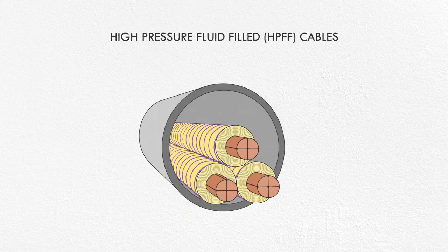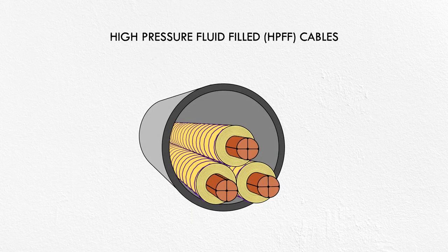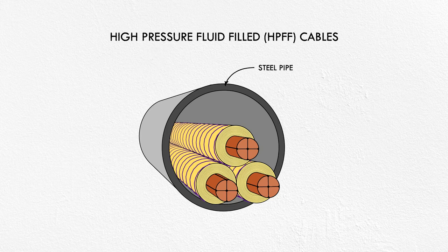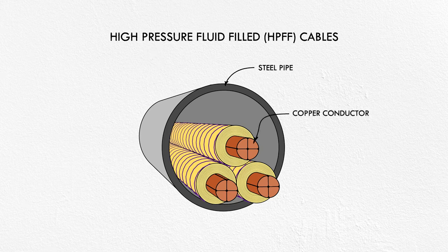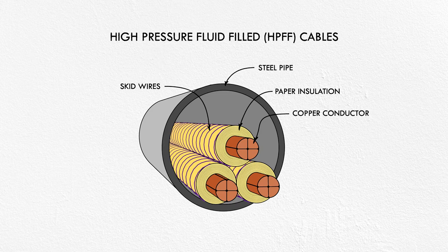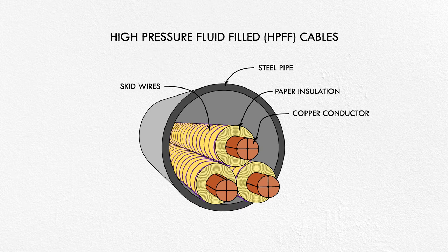Well, you need a better insulator than just air. One of the more popular options of the time was to use high pressure fluid filled cables. This design starts with installation of a steel pipe below the ground with access vaults spaced along the way. Copper conductors are surrounded with many layers of paper insulation. Next, a protective layer of wire, called skid wire, is spiraled around each one to protect the paper from damage and allow for easy sliding along the pipe during installation.